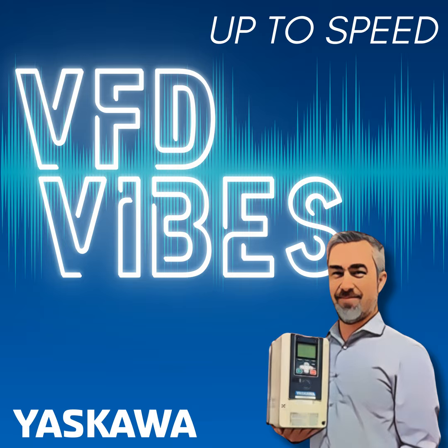And there are advantages to this. First of all, the voltages are all symmetrical, line to line and line to ground, and they are balanced. If we have identical phase windings, we'll have balanced voltages. Balanced means that they are all 480.0 volts line to line. The other advantage of solid grounding is any capacitively coupled transients from the transformer primary are shunted to ground.